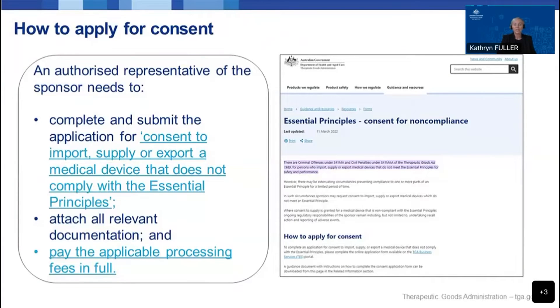If you're seeking consent for non-compliant devices, an authorised representative of the sponsor will need to complete and submit the consent application form, which is hosted on the TGA Business Services site. A link to this can be found on the TGA's Essential Principles Consent for Non-compliance webpage, which also provides a copy of the guidance document on how to complete the application form. In the application, you'll need to upload all relevant documentation such as the risk mitigation strategy and implementation plan, and pay the applicable processing fees. The delegate of the Secretary will take all relevant information into consideration when determining whether to grant consent, and a notification will then be sent to the sponsor advising them of the outcome.